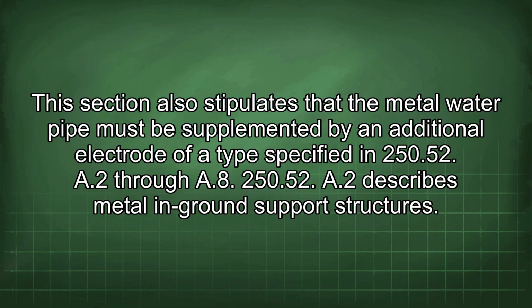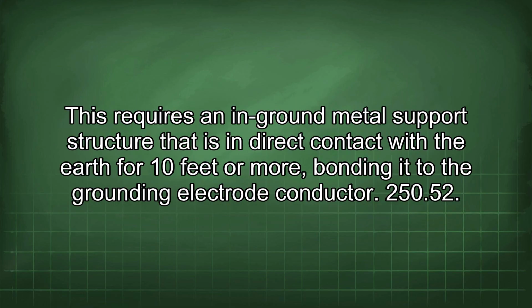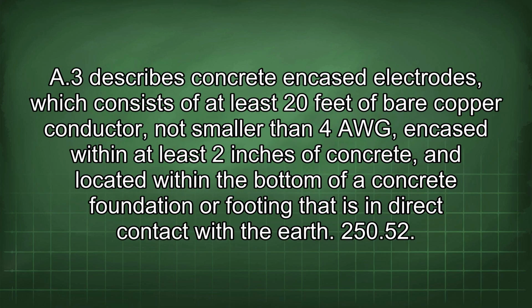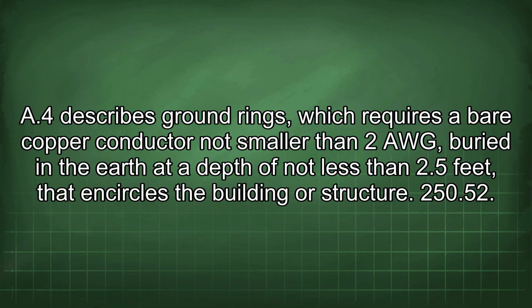250.52(A)(2) describes metal in-ground support structures. This requires an in-ground metal support structure that is in direct contact with the earth for 10 feet or more, bonding it to the grounding electrode conductor. 250.52(A)(3) describes concrete-encased electrodes, which consist of at least 20 feet of bare copper conductor, not smaller than 4 AWG, encased within at least 2 inches of concrete, and located within the bottom of a concrete foundation or footing that is in direct contact with the earth. 250.52(A)(4) describes ground rings, which require a bare copper conductor not smaller than 2 AWG, buried in the earth at a depth of not less than 2.5 feet, that encircles the building or structure.